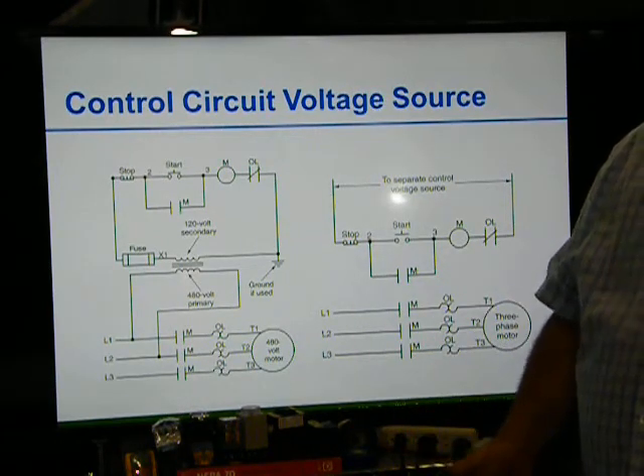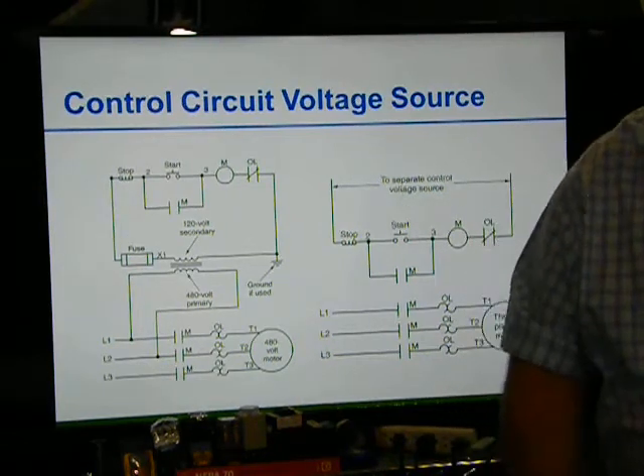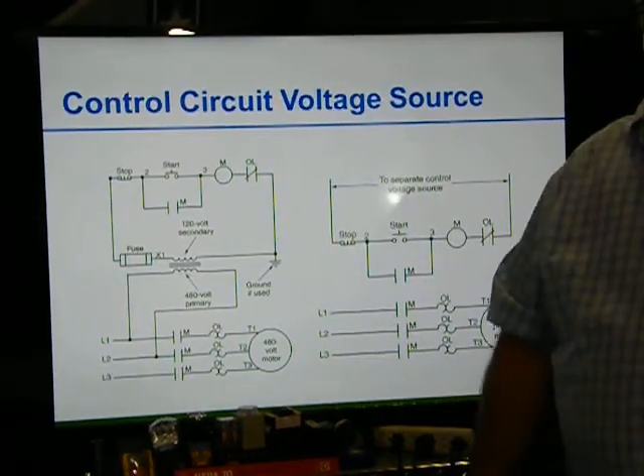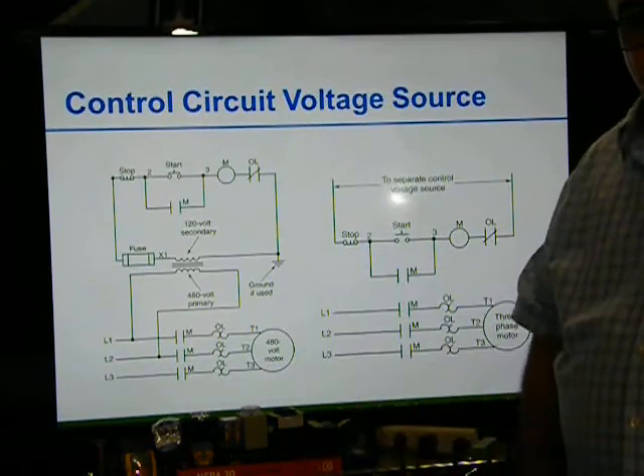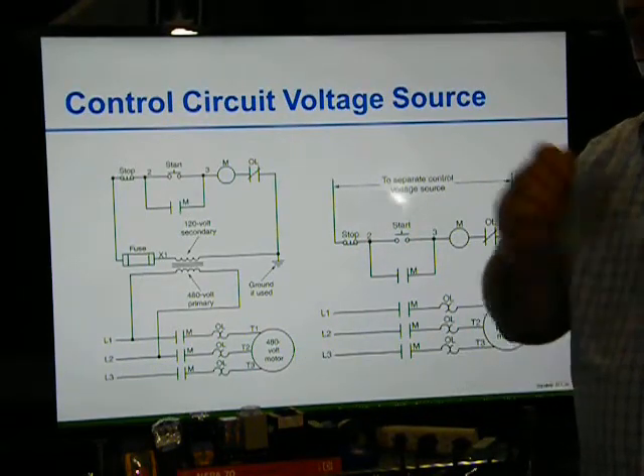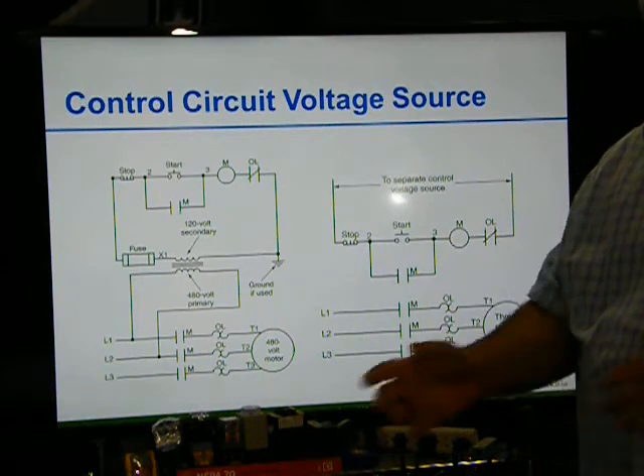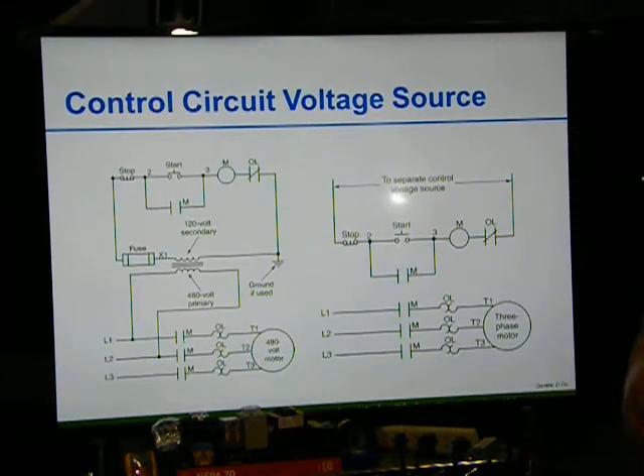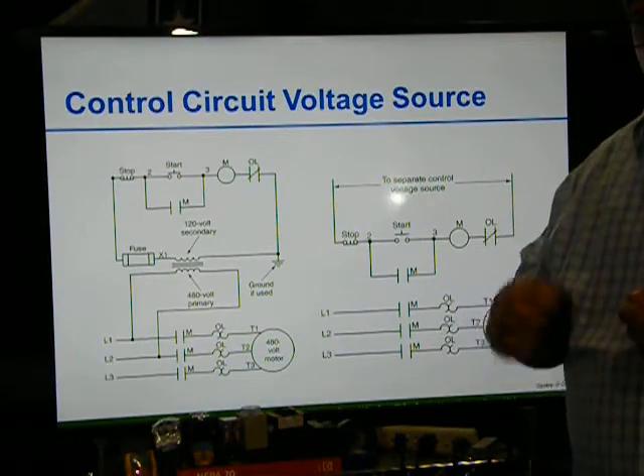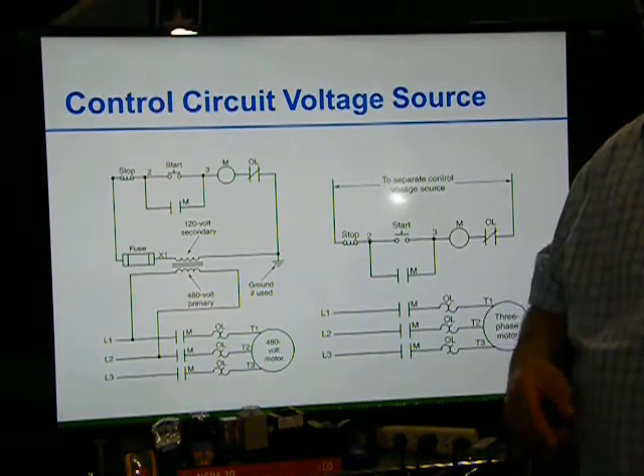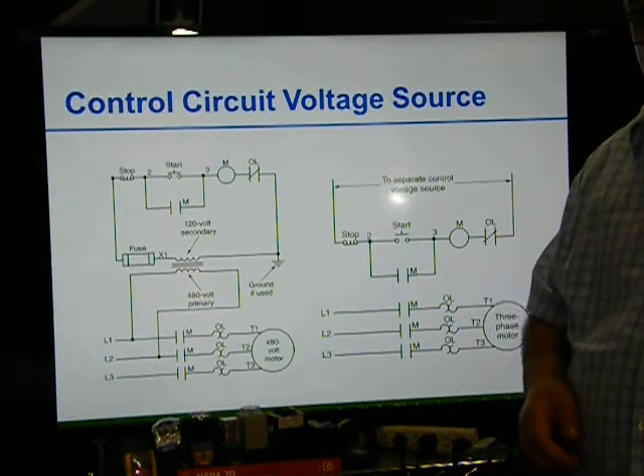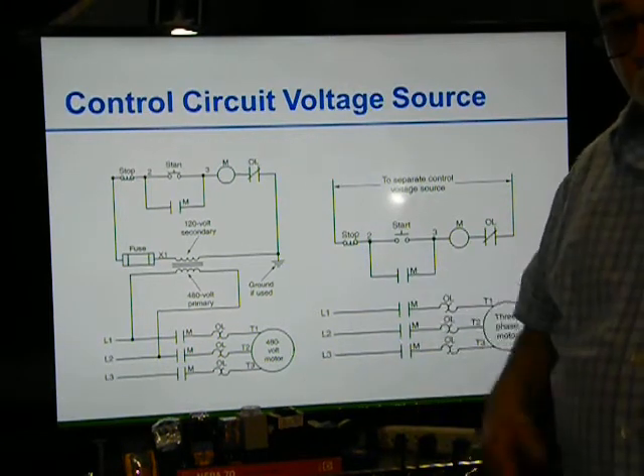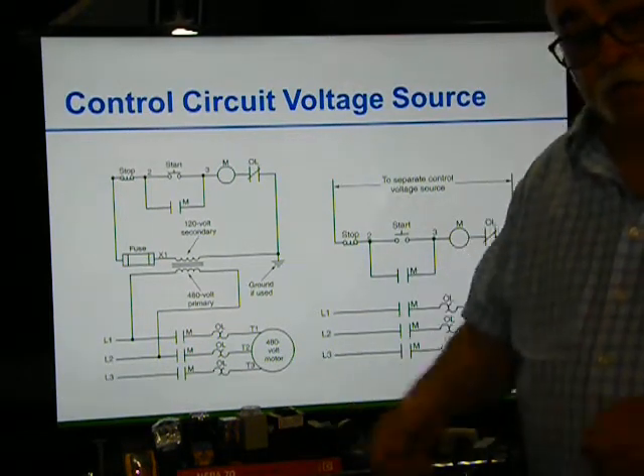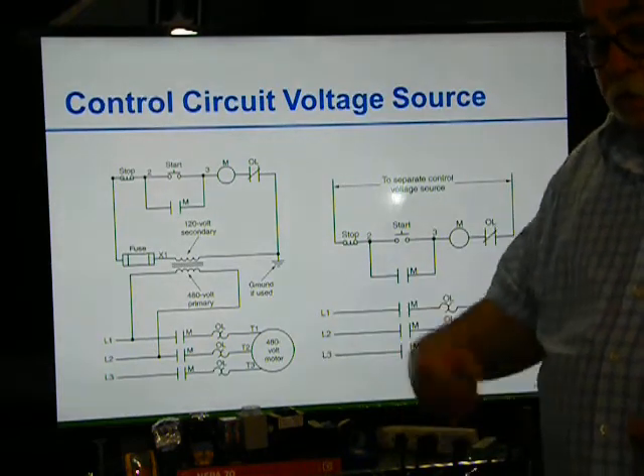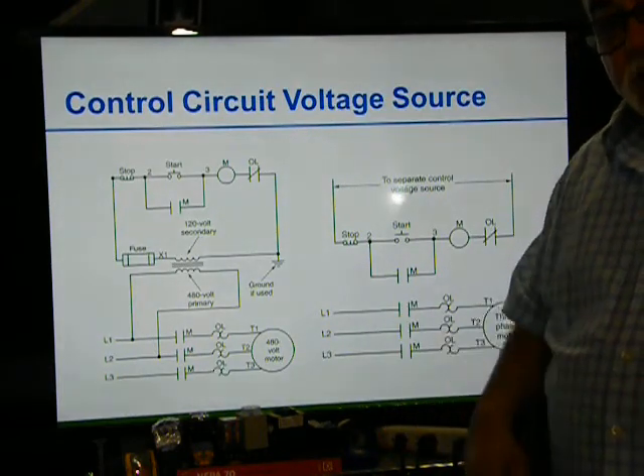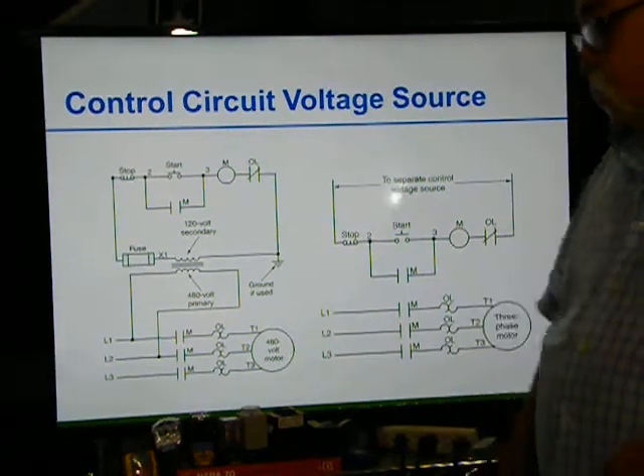Not all windings. We have that problem with transformers. We had a smaller transformer and we changed it out to a bigger transformer. We're adding things. But luckily, before we changed out the transformer, I took a rotation reading. Which way is the current turning? Do the same thing with the motor. Check your rotation, your power. Power's going in one direction. Take your rotation, see which direction your motor's turning, and when you hook it back up, make sure your rotation is the same way.